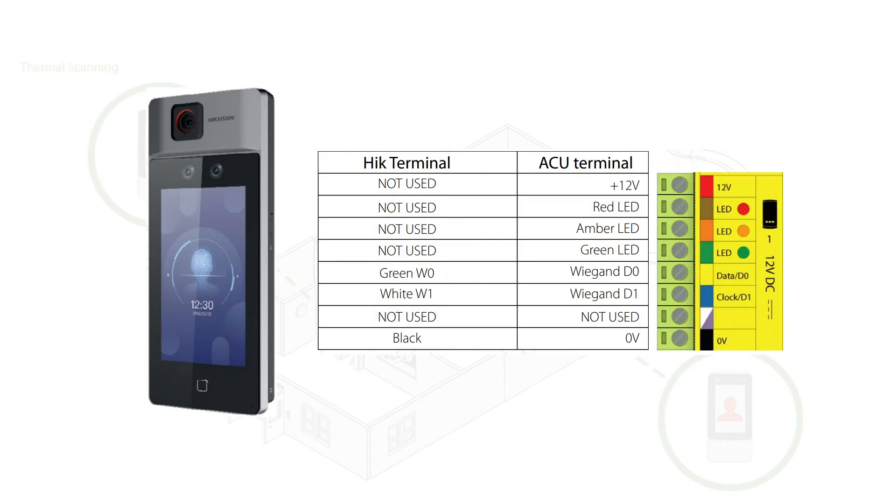The scanner will connect to the reader port of the NET2 plus control unit using the Wiegand D0, D1, and ground connections.